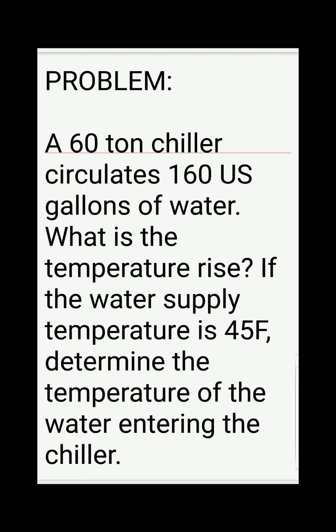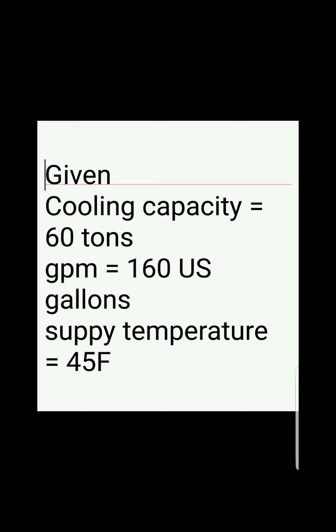So first, we need to determine our given information. So we've got the cooling capacity of the chiller is 60 tons and the water flow rate or GPM of 160 US gallons per minute. Also, we have the supply temperature equal to 45 Fahrenheit. So here we've got two unknowns: the temperature rise or the change in temperature, the delta T, and the temperature of water entering the chiller. It's also called the return temperature.